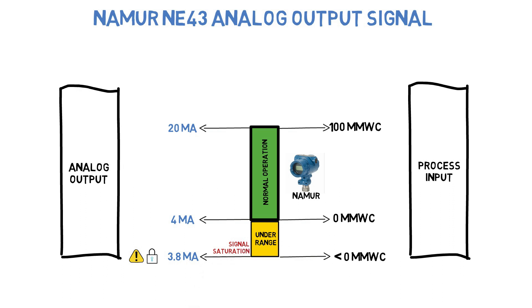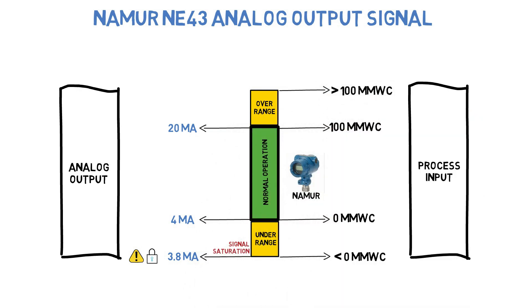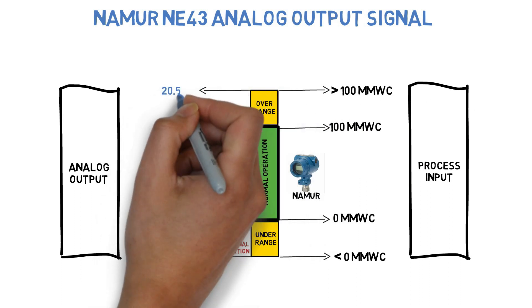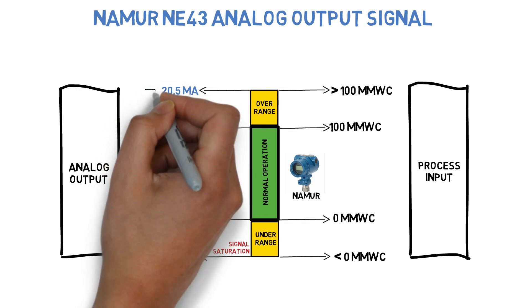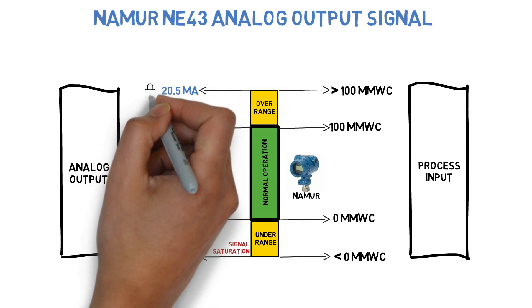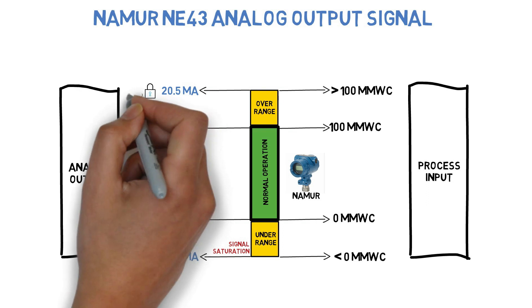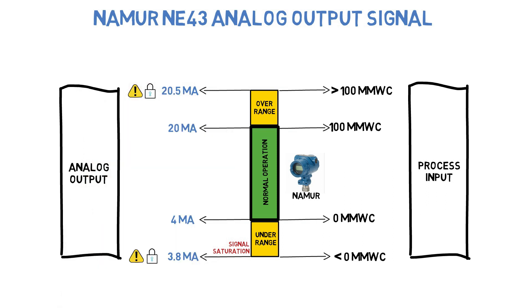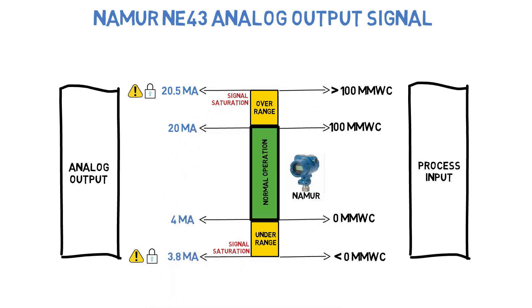If the process input increases above the upper range value of the transmitter, the analog output also increases between 20 and 20.5 mA. If the process input exceeds the upper range value, the analog output holds at 20.5 mA with a warning to the control unit. This over-range signal is also referred to as signal saturation.